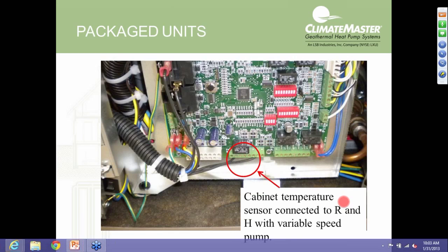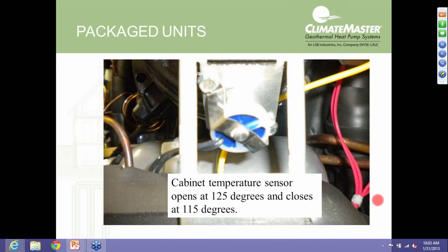Now, with the variable speed pump option, we have a cabinet temperature sensor, and in the package heat pumps, it's just a bimetal switch that is normally closed that we send 24 volts to, and it's powered from R and H over on the P2 connector here that's circled.